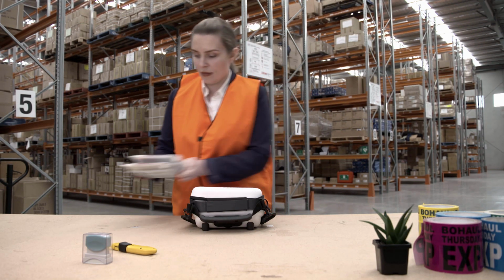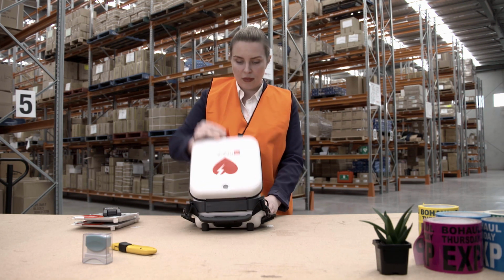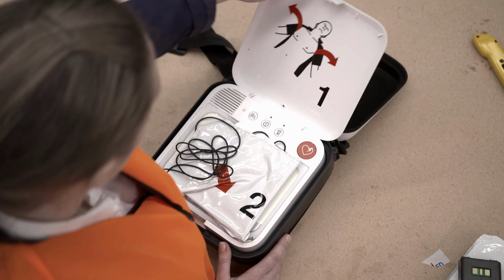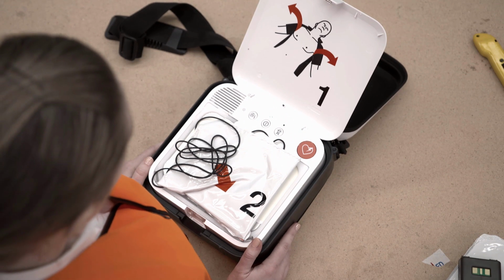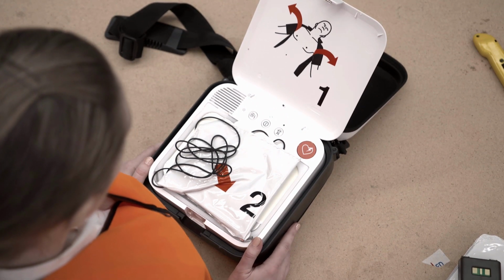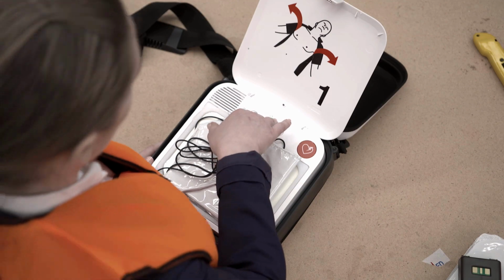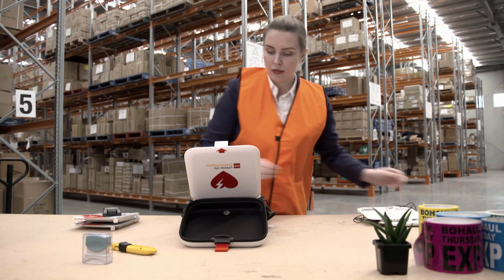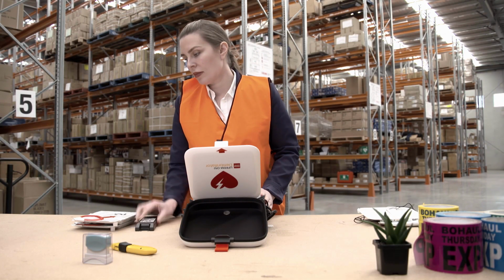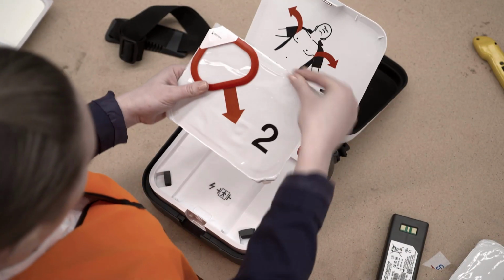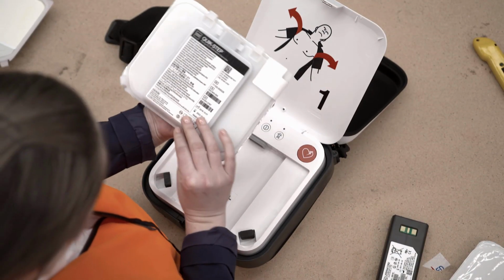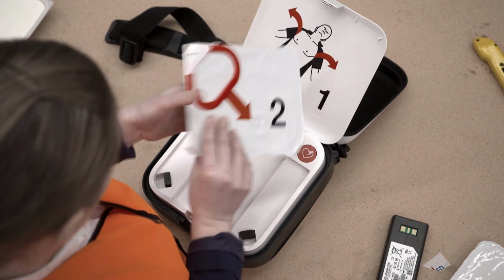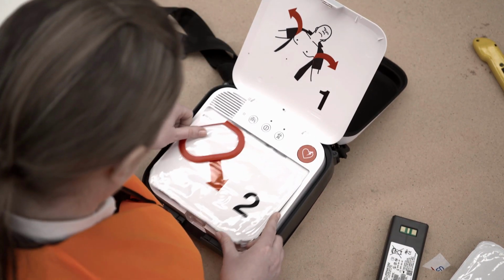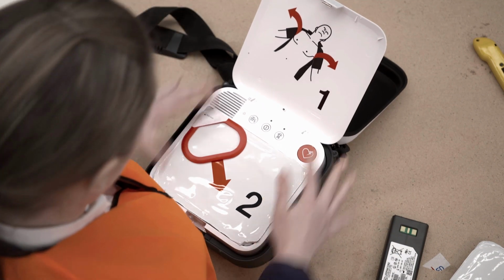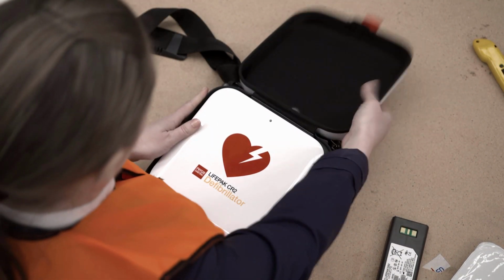Here we will show you how to change the batteries and pads of the CR2 Essential defibrillator. To replace the pads, first open the lid of the defibrillator. Hold the off button down to turn off the device. Lift out the used or expired pads pack and dispose of it. Inspect the new pad pack seal and expiry date. Close the lid of the device. The new pad pack is ready for use.